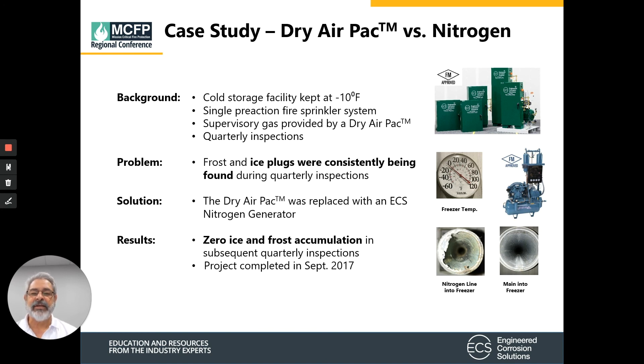Case study one: a cold storage facility kept at minus 10 degrees Fahrenheit with a single pre-action system. The supervisory gas was a Dry Air Pac with quarterly inspections, and the problem was frost and ice plugs were consistently found during quarterly inspections. The solution was to remove the Dry Air Pac and install a nitrogen generator. The result: no ice plugs and no frost accumulation in subsequent quarterly inspections. This project was completed in September 2017.